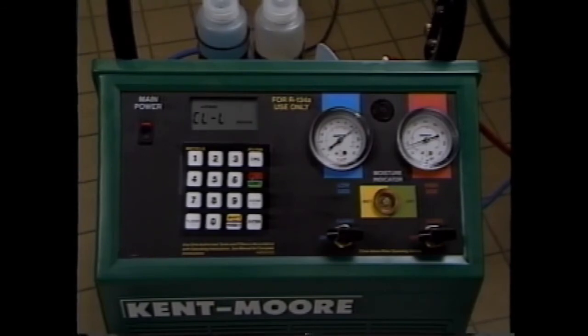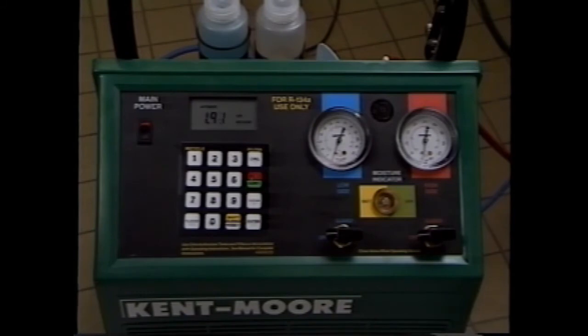CLL will appear on the display during this process. When the clearing is complete, the unit will automatically start the recovery process, and the screen will show that the unit is in the recover mode of the automatic cycle. The weight of refrigerant being recovered will also be displayed. After initial recovery has occurred, the compressor shuts off automatically.